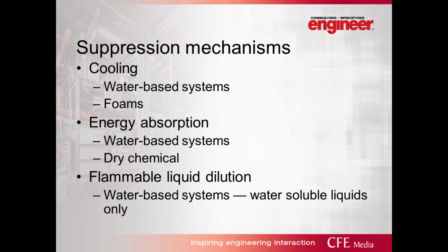The next mechanism is energy absorption. This is basically taking energy away from the fire, again, mostly to reduce the heat and take that portion of the fire triangle away. Again, water-based systems are very good for energy absorption. They cool and they absorb energy at the same time with the way that they work. Dry chemical suppression agents are also very, very good at absorbing energy, and that is one of their main mechanisms for fire suppression.